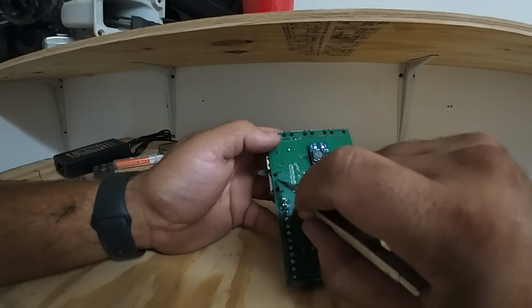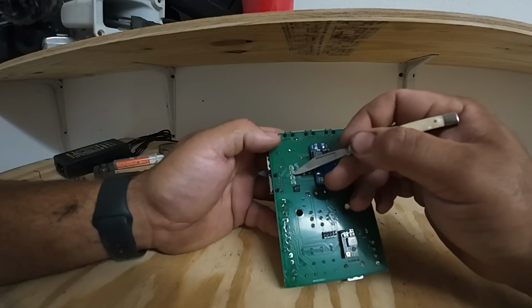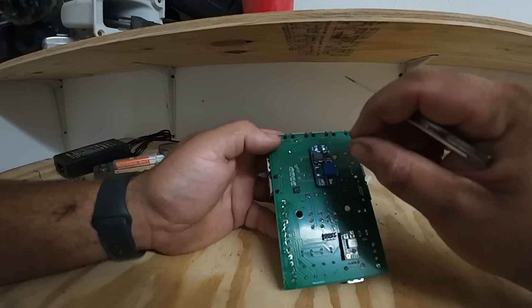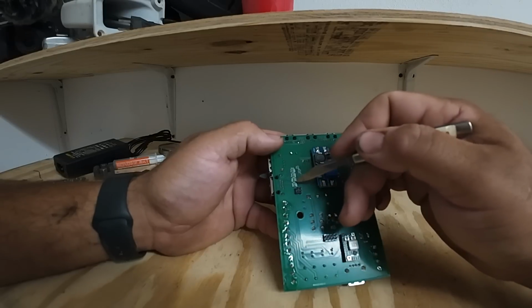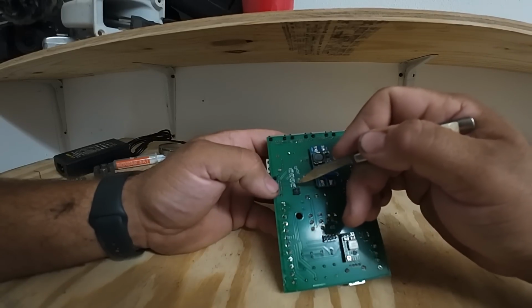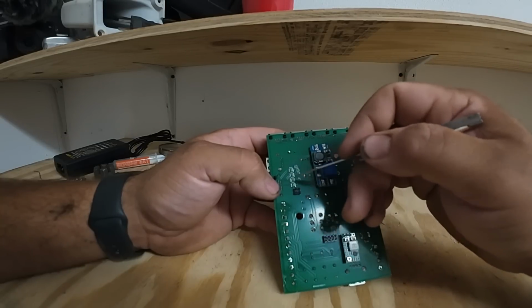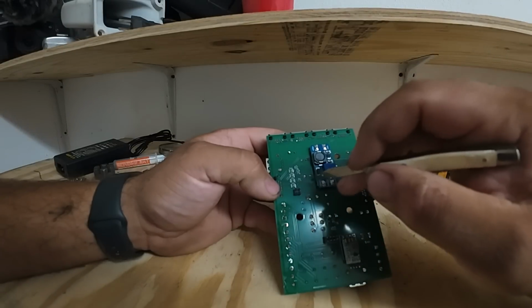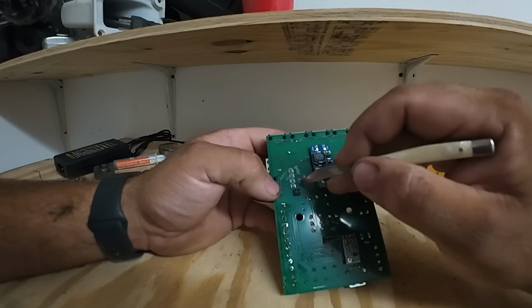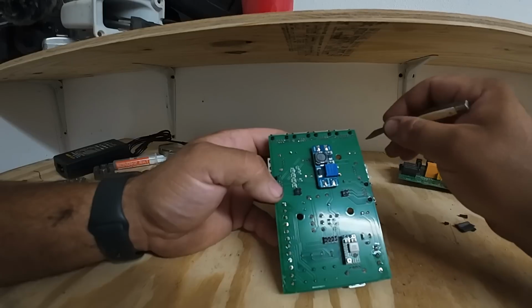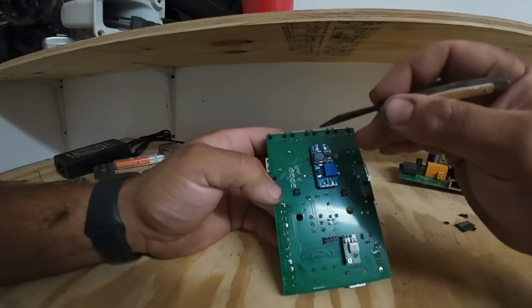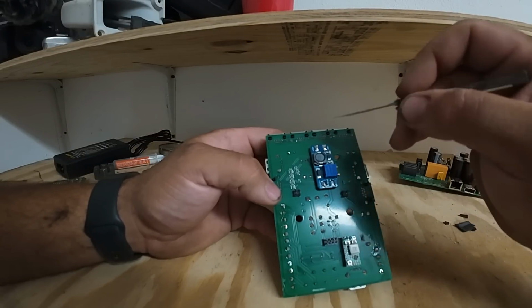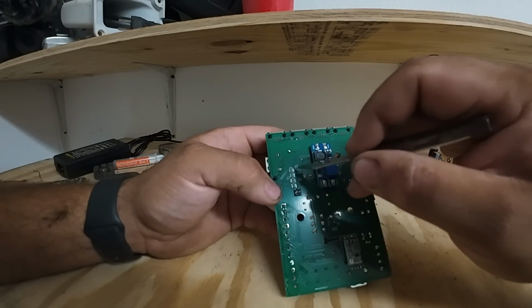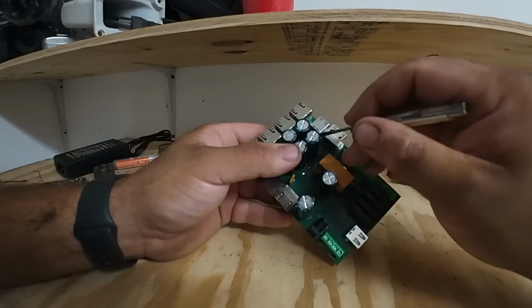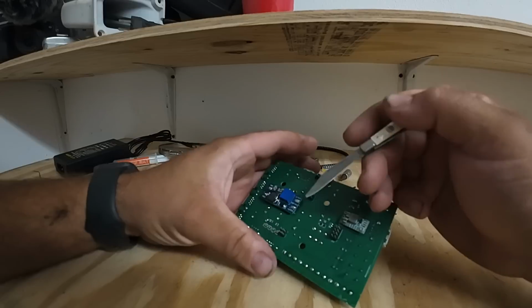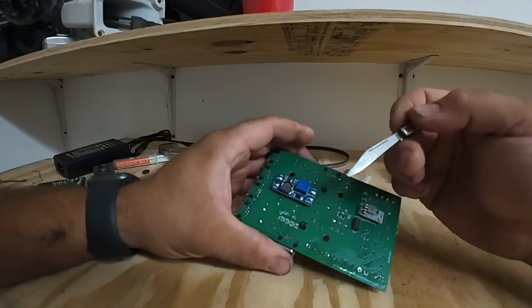The 4 to 20 milliamp sensors come back in here. We've got 4 thermal fuses. If any of the sensors short, this will limit the current that's available inside the tank, hopefully low enough that you can't create a spark. It limits them to about 40 milliamps. We've got a set of small resistors. These resistors are what changes the current to a voltage. We talked about that in the first video. Anyway, these are then carried via the other side of the board through some vias and back through these 4 pins, and these 4 pins are what connects back to the LabJack.